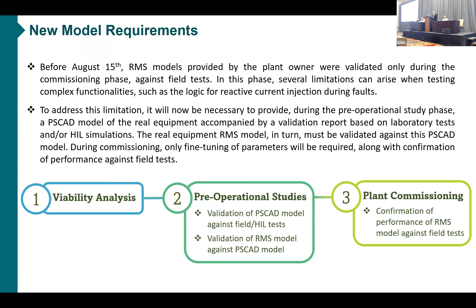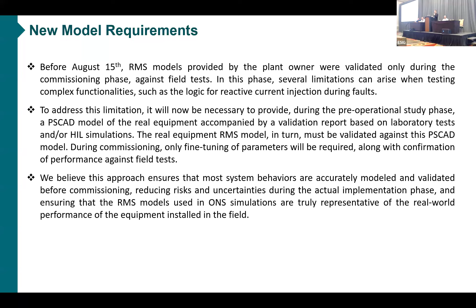And now, since we are doing all these validations during the pre-operational studies phase, using HIL simulations most often as a benchmark, during commissioning we will only do fine tuning of parameters with confirmation of performance against field tests. So we believe this approach would ensure that most system behaviors are accurately modeled and validated before commissioning, to reduce risks and uncertainties during the actual implementation phase, and to ensure that the RMS models used in our simulations are representative, because we really need to get our trust in our models back, because we lost that in the August 15th event.